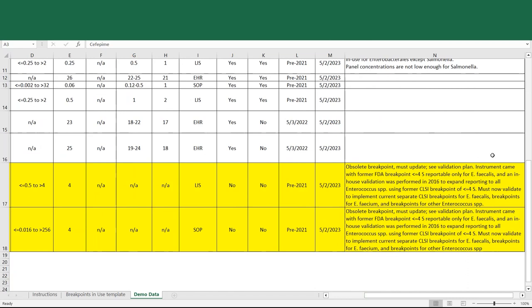And then further comments are provided saying that the instrument came with former FDA breakpoint of less than or equal to 4 for enterococcus faecalis. In 2016, the laboratory did a validation to expand reporting to all enterococcus species using the former CLSI breakpoint of less than or equal to 4, but that they now must do another validation to implement the current separate CLSI breakpoints for enterococcus faecalis, for enterococcus faecium, and for other enterococcus species.